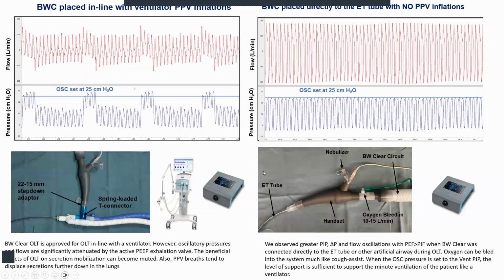And so what we did is we took the BiWaze Clear after the final software release, placed it in line with the ventilator. And there were lots of things that we were trying in order to improve the therapeutic effect with these flow and pressure waveforms. And what we were showing is that when you set your oscillation at 25 centimeters of water pressure, and maybe you're ventilating at 30 or 25, you're on the expiratory phase, and that's kind of where these devices work the best. The flow's coming out, and we're applying these oscillations, and they're dipping down.